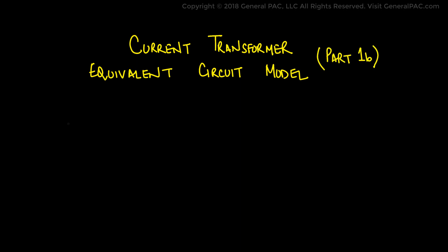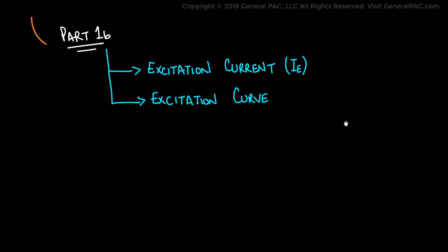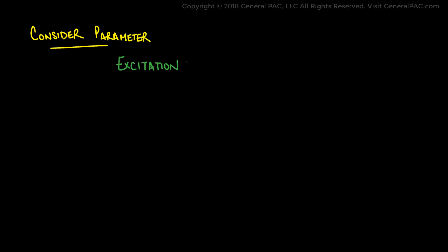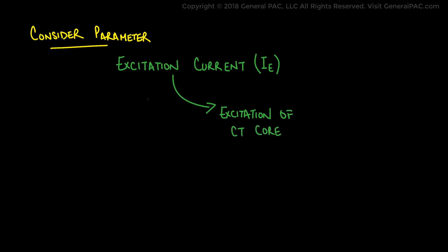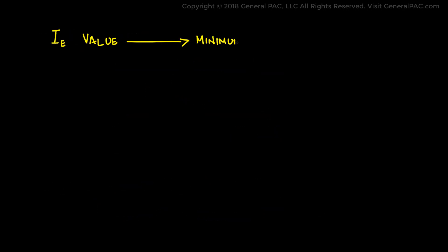Current Transformers Equivalent Circuit Model, Part 1b. In Part 1b of this series, we shall continue from our previous part and talk about excitation current and the excitation curve in much more detail. The excitation current i.e. is responsible for the excitation of the CT core — it actually makes the CT work in real life. But it is also the current that is lost through the magnetizing branch and corresponds to the CT error. The more the excitation current i.e., the more the errors or the more saturation that the CT will observe. The value of the excitation current should be kept as minimum as possible.